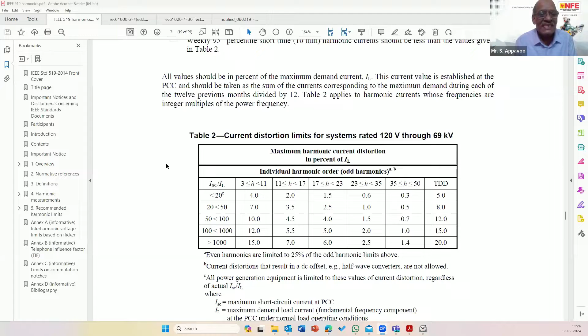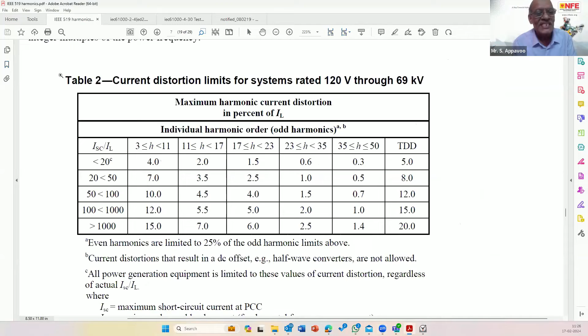Hope the screen is visible now. In the screen you can see that the permissible TDD is related to the ratio ISC by IL, shown in the first column. For less than 20, if the ratio ISC by IL is less than 20, the TDD should be strictly limited to less than 5%.